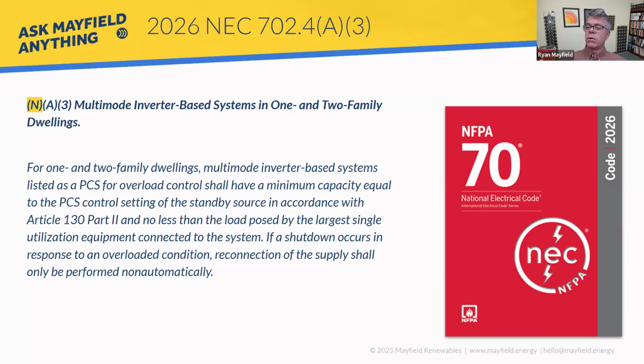Then we are going to look at Article 130, and there's where we see that largest single utilization equipment connected to the system. Part of the process was getting people on the code making panel comfortable with, well, what happens if I have a 60 amp inverter and 200 amps of load tries to start on? What's going to happen? The idea here is you see that if the shutdown occurs, it has that overload control, so we're going to have this non-automatic reconnection to that supply - making sure we're not going to have something trying to kick on and off, on and off, potentially causing some sort of fire situation or hazard.